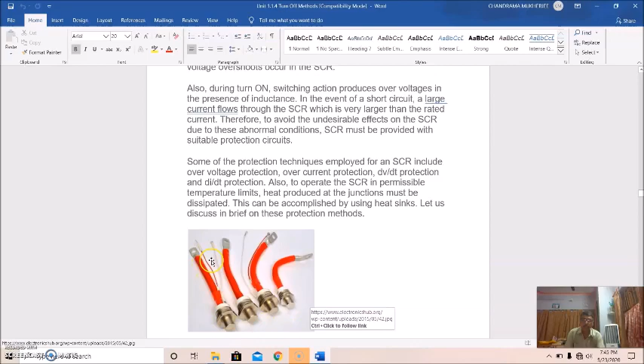Now, overvoltage. The greatest cause of failure of an SCR is transient overvoltage. Overvoltages often lead to unscheduled turn-off of the SCR, and may lead to permanent destruction of the SCR if the reverse transient voltage is more than the reverse recovery voltage across the SCR. There are several causes for overvoltages, like commutation, chopping, lightning, etc.